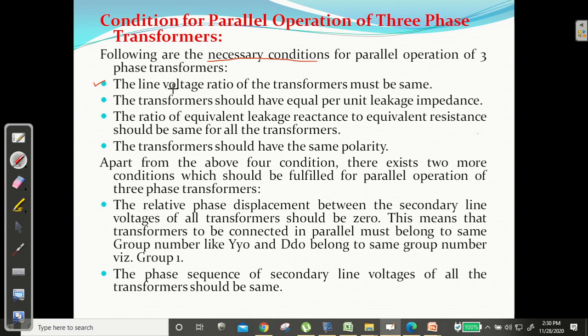First, the line voltage ratio of the transformers must be same - the voltage ratio, both primary and secondary, of all transformers connected in parallel must be same. If the ratio becomes different, circulating current can start flowing. We'll discuss this point later on.